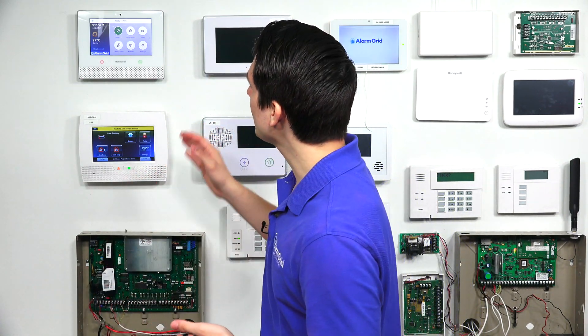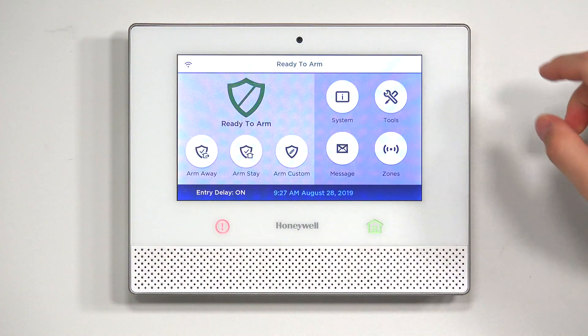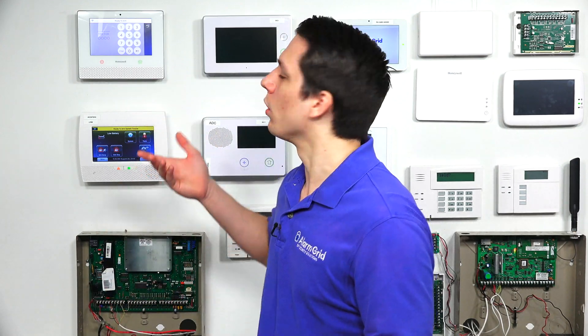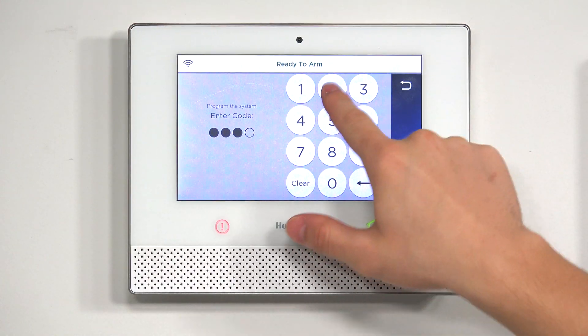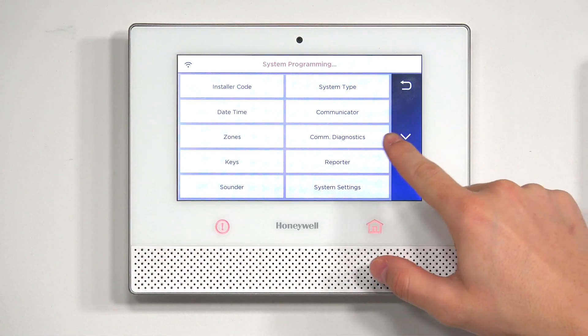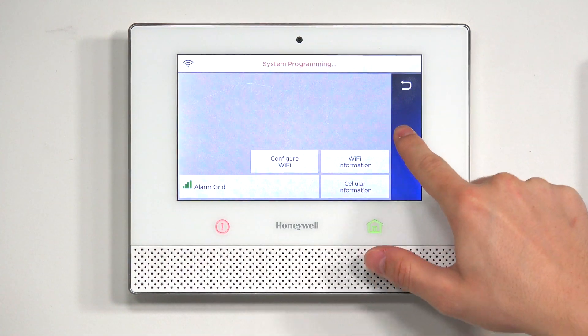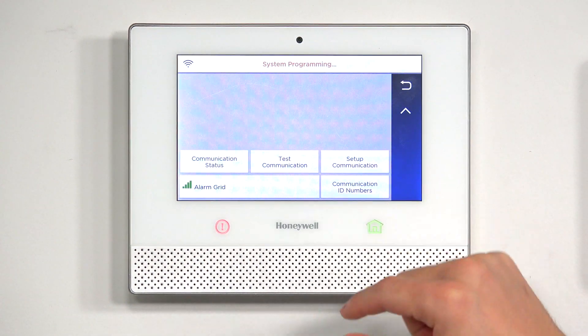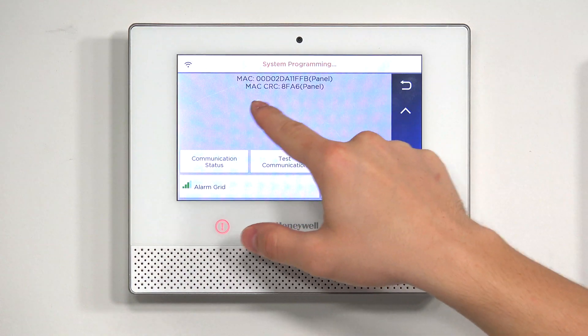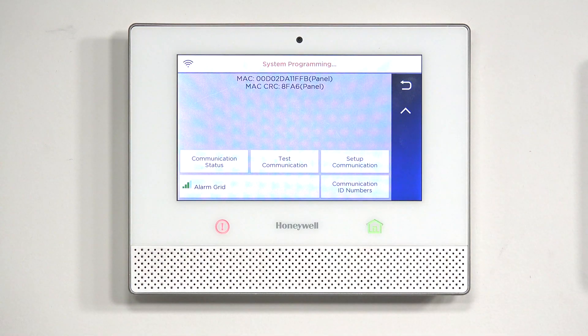To find the Mac and CRC on the Honeywell Lyric, at the main screen you're going to tap Security, then go to Tools. This is where you'll need the installer code — the default is 4112. Then go to Program, hit Comm Diagnostics, hit the down arrow, and you should see Communication ID Numbers at the bottom right. Tap on that, and you can see the Mac address and the CRC on the panel right there.